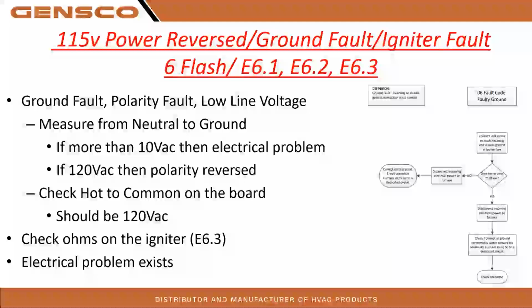So, ground fault, polarity fault, or low line voltage. So you're going to measure neutral to ground. If you get more than 10 volts AC, then there's an electrical problem within the home, right? If you get 120, then the polarity is actually reversed. So you should check hot to common on the control board. There should be 120 volts there. Check ohms of the igniter, 6.3. And then of course, electrical problems could exist within the home.